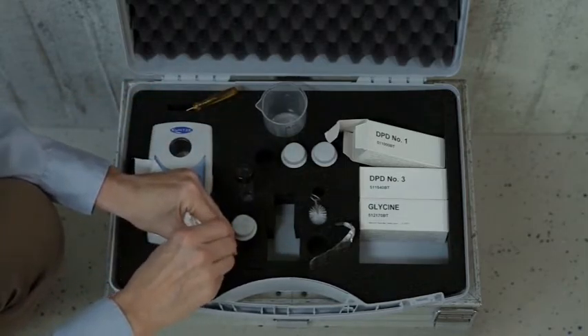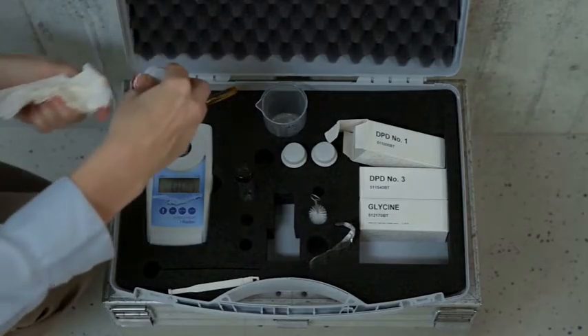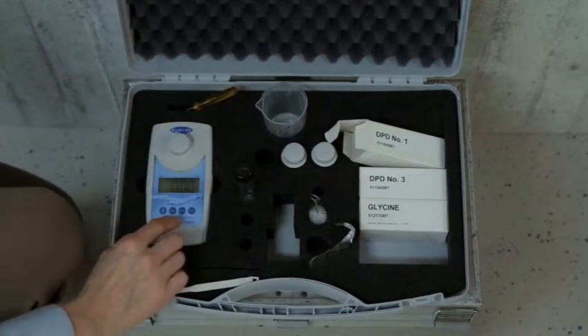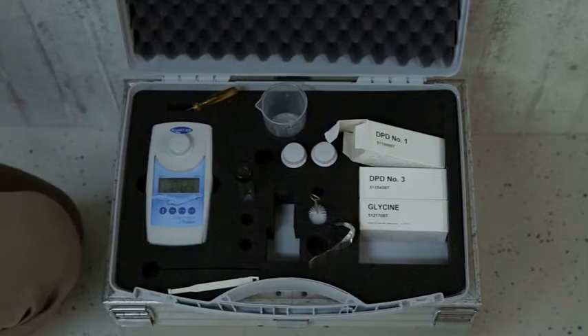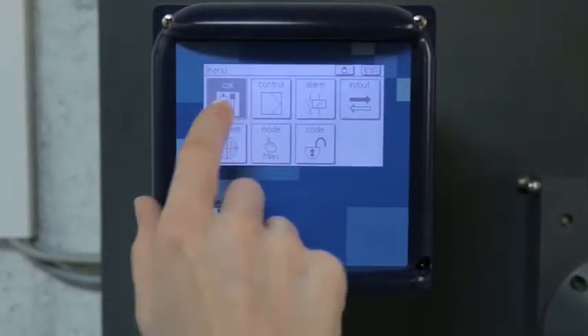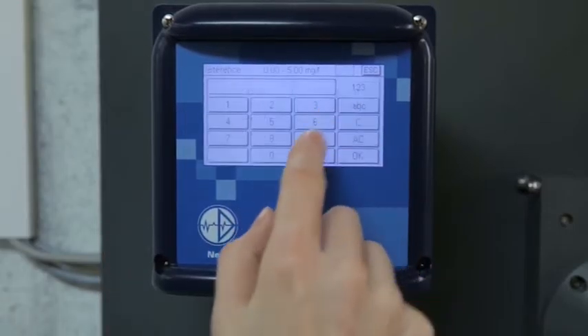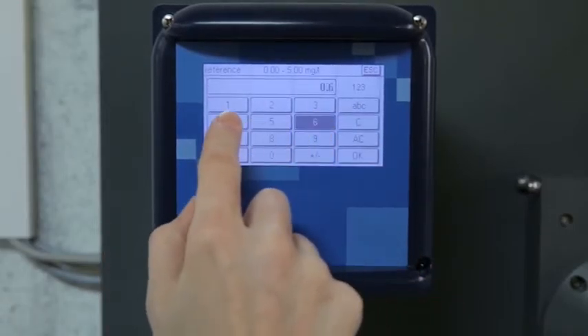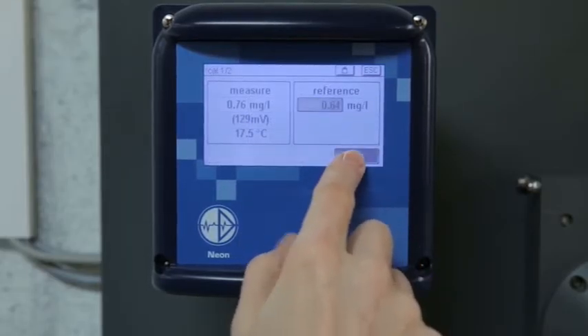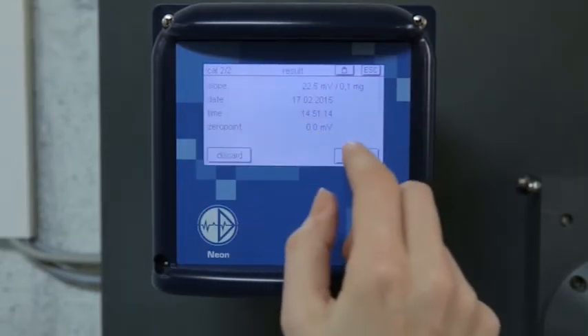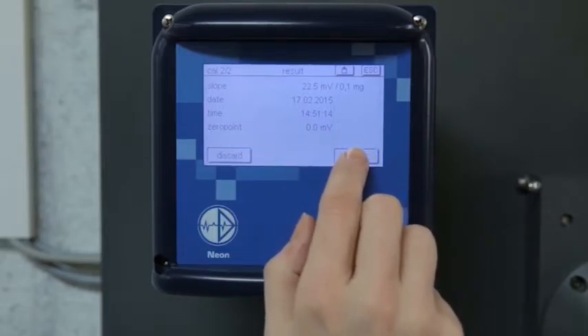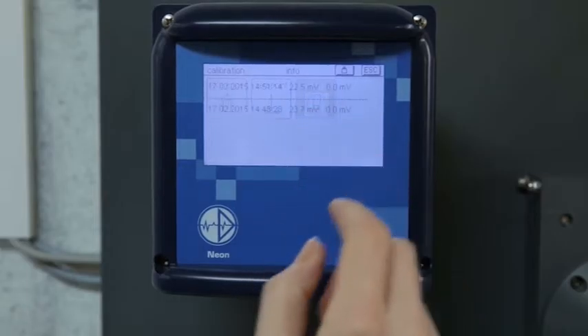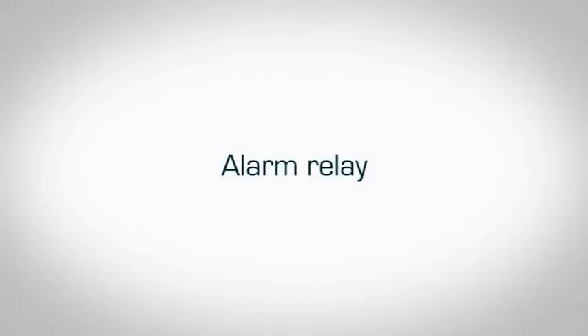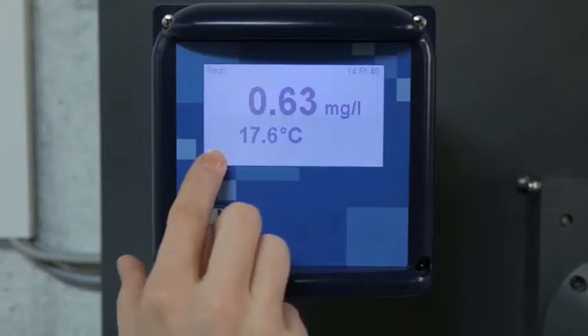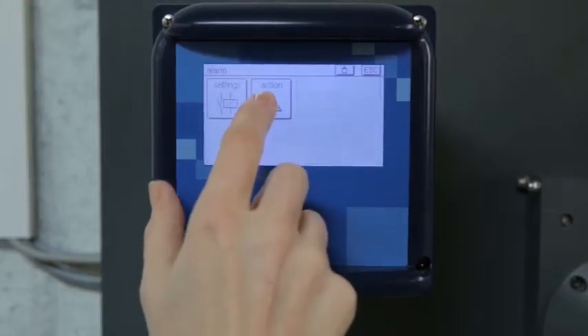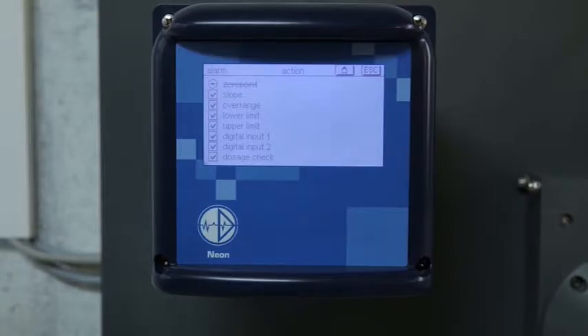Take a water sample at the sample point and determine the chlorine content. Use the reference value for calibration. We measured 0.64 milligrams per liter. On the basis of this value, the instrument then calculates the sensor-specific data. In this case, the slope is 22.5 mV. The info menu displays the last 10 calibrations. The instrument has various alarm functions. In the Alarm Action menu, you assign the alarm relay to the events.